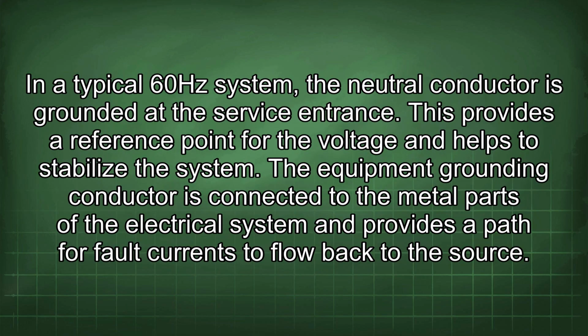In a typical 60 Hz system, the neutral conductor is grounded at the service entrance. This provides a reference point for the voltage and helps to stabilize the system. The equipment grounding conductor is connected to the metal parts of the electrical system and provides a path for fault currents to flow back to the source.